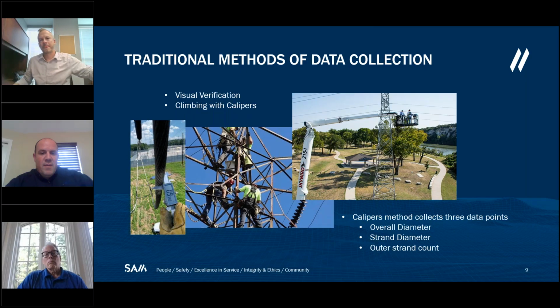The method they were going to go with was climb up with calipers, take a measurement of the overall diameter, measure the diameter of each individual strand, and where they could, at a dead end or something, try to get a count of the outer strands. Then take those 3 data points and use them to verify the conductor type based on manufacturer's data. So they could use the manufacturer's rating, which is the first bullet point in NERC FAC-008 in the text on how to do this. One of the other traditional methods is visual verification.